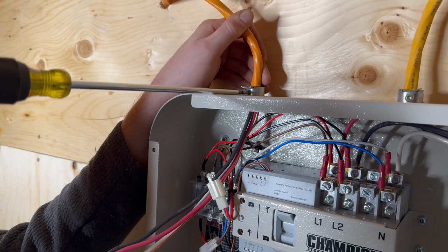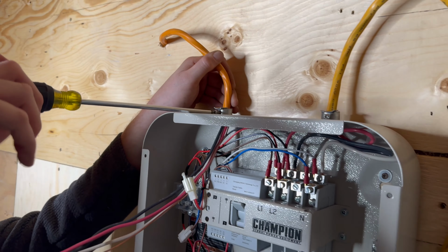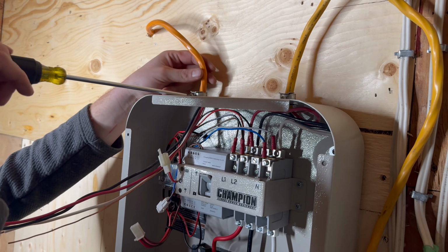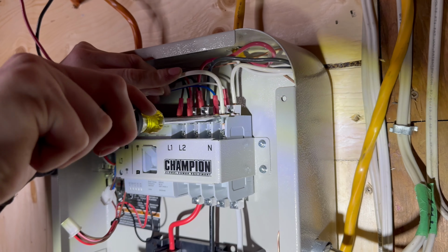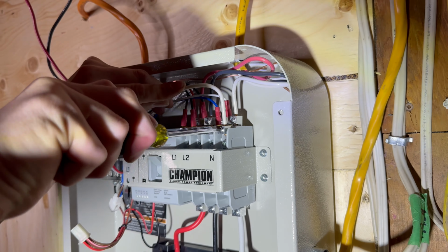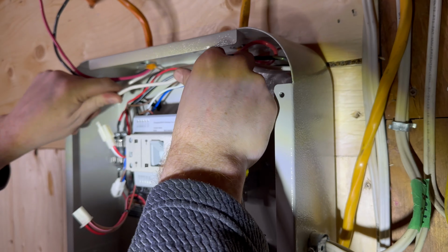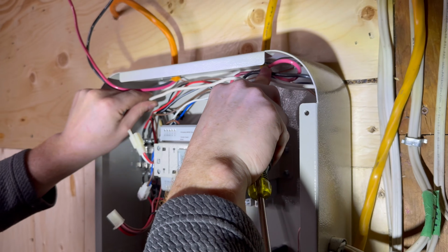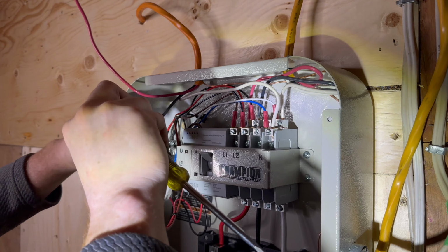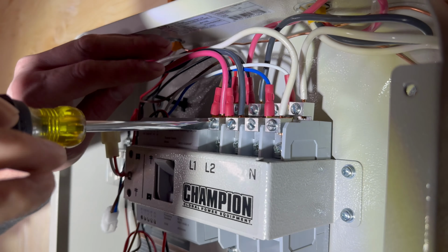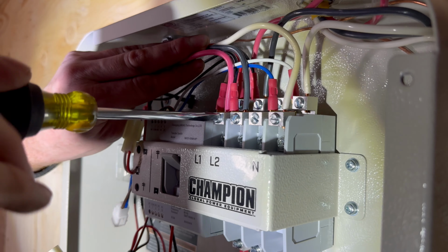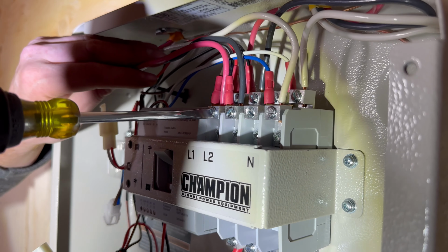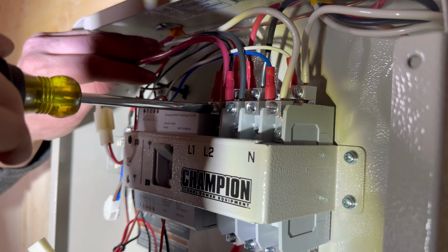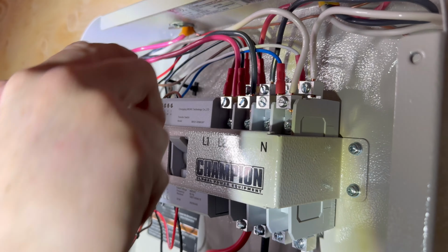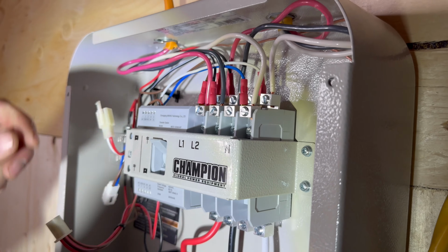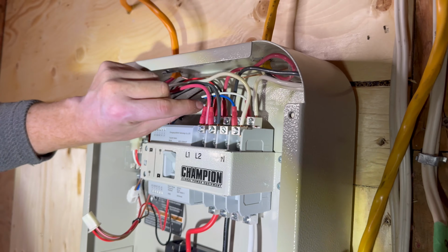Finish up the inlet side wiring in a similar way as you did when you were working with the other heavy cable. So the ground wire goes to the ground lug on the panel. The white wire goes to the neutral lug, marked N here, and the black and the red go to the L1 and L2 lugs. Notice how these connections are made in the front set of lugs, whereas before your heavy cable connections were made to the back set of lugs.